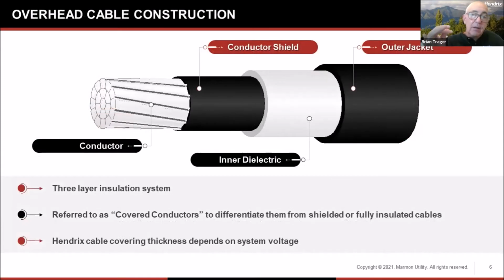And the 3-layer insulation system is the first. We're going to have a semicon, and that semicon is there for the same reason we use a semicon layer on underground cable, so that when I have a short circuit or ground on the outside of that outer jacket and full voltage stress across the insulation wall, that semicon will put the whole outside of the individual strands as well as the interstices at the same potential. So we smooth out the electric field, minimize the partial discharge, give us a higher BIL, and give us a longer useful service life. The second layer you can see is a high molecular weight, low density polyethylene.